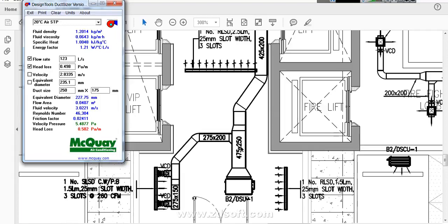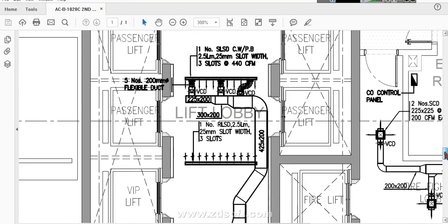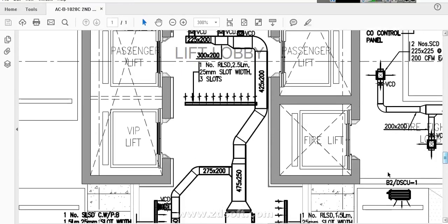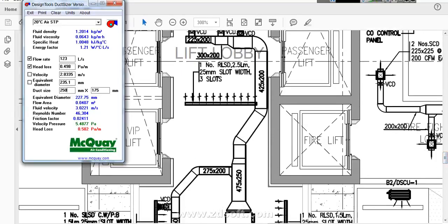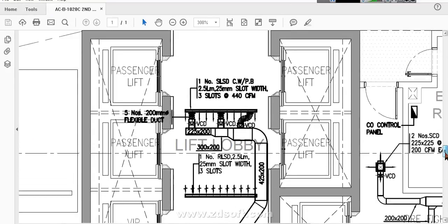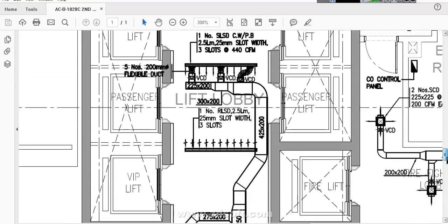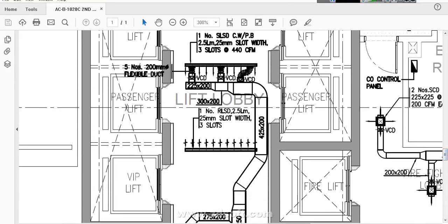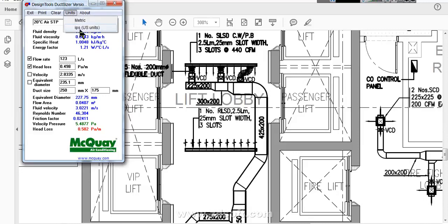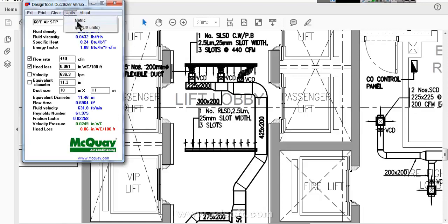So this is the way you need to find out the duct sizing. Here we will calculate one more size. Here the CFM is 440 CFM. Again we will go back to the old unit. 440 CFM is equal to 208 liters per second. Here 0.49 or 0.5 there is no problem.